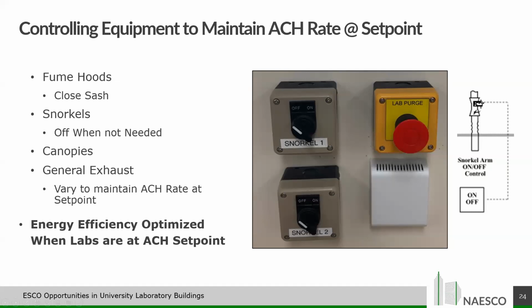As Paul mentioned, there are many aspects to the lab space, and one of them is fume hoods, which is your main driver to your exhaust. However, we do have other items as well. Snorkels, for example. We've been in universities where controlling the snorkels was all about balancing the building, and they were that important. You get a little CFM in every snorkel, and you multiply it times hundreds and hundreds of snorkels in the space. It starts to add up to quite a bit of energy and quite a bit of airflow.